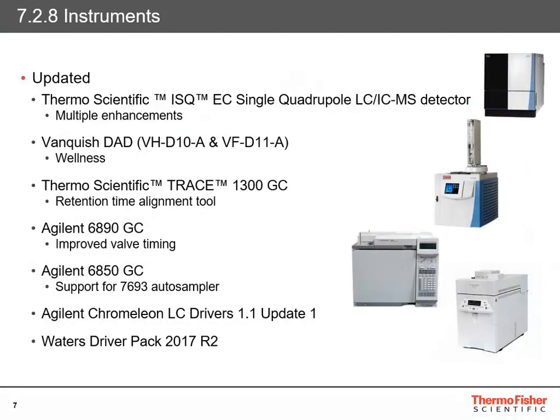There is an updated driver for the ISQ EC single quadrupole, released with 7.2.6, with multiple enhancements. It is now possible to acquire MS data in profile mode. The instrument method editor now includes an option to automatically create temporary channels, which can be used as inputs for mass-directed fraction collection. It now supports Smart Startup, Smart Standby, and Smart Shutdown. The instrument method script now supports assignment of injection and sequence custom variables for method settings, allowing variables to be brought in from outside the method itself. It is now possible to exchange information via the Windows clipboard between the instrument method scan table and the processing method component table.